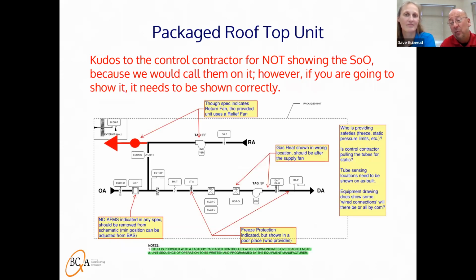You know, my second page here is kind of the proof of the pudding. As the commissioning provider, we had to review the submittal to actually find out what was in there. The system talked about a return fan, but the submittal said it's just a relief fan. The gas burners, typically on rooftops, are on the leaving side of the fan. They show a mixed air freeze protection device, and that, here in Wisconsin, doesn't make any sense at all. And then they even mentioned an airflow monitoring station, which again, we couldn't find anywhere.